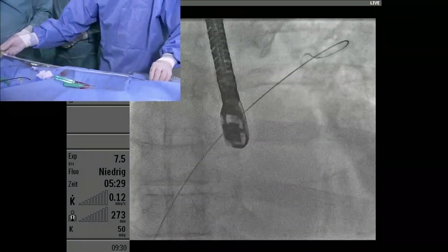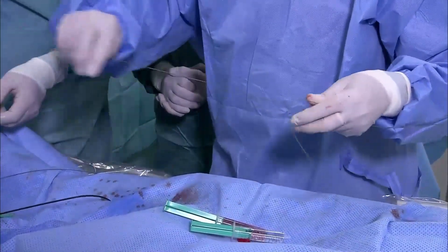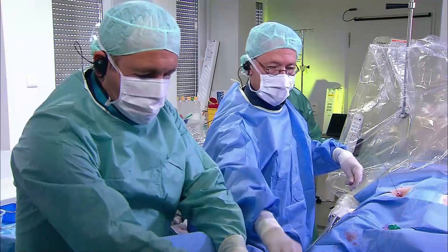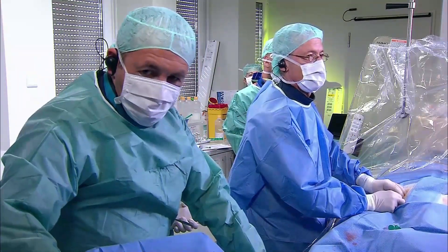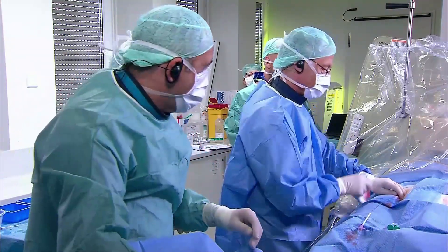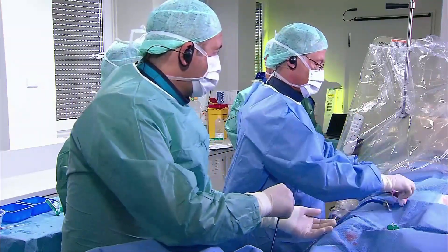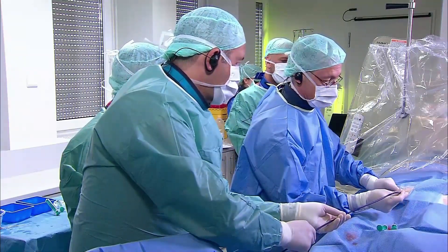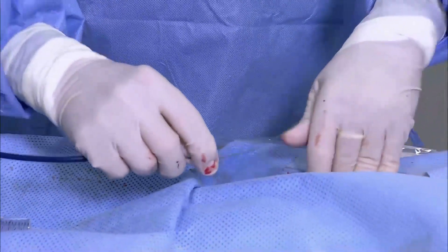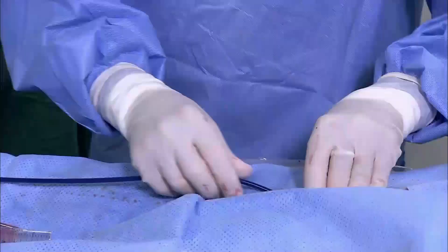The question was about endothelialization and whether this will affect the readings, and what the experience was in that area. Deddy, if this gets covered by tissue, would you still be able to measure? From our experience in animals we have more than one year post-implantation experience, also with histopathology analysis, and we didn't see any tissue overgrowth over the sensor. But if that would happen, then you cannot measure anymore. We believe that even with a small level of growth, we can still measure.